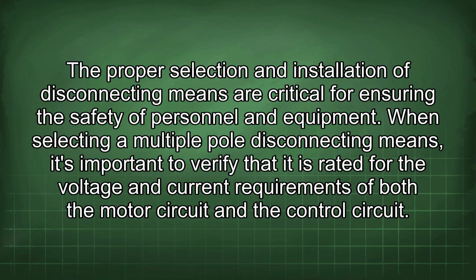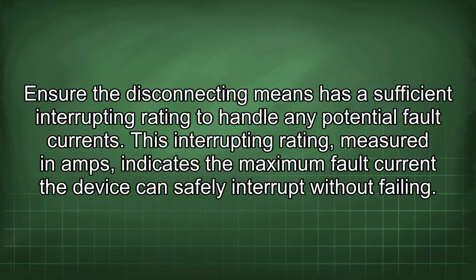When selecting a multiple pole disconnecting means, it's important to verify that it is rated for the voltage and current requirements of both the motor circuit and the control circuit. Ensure the disconnecting means has a sufficient interrupting rating to handle any potential fault currents. This interrupting rating, measured in amps, indicates the maximum fault current the device can safely interrupt without failing.